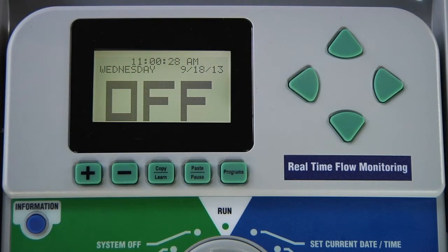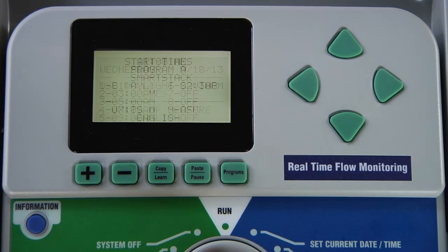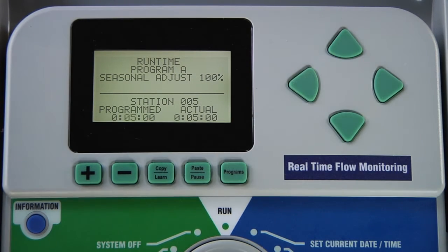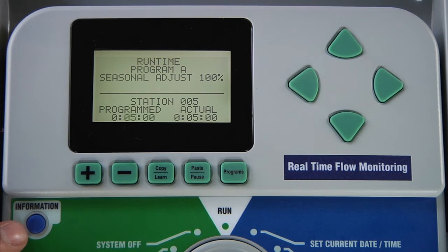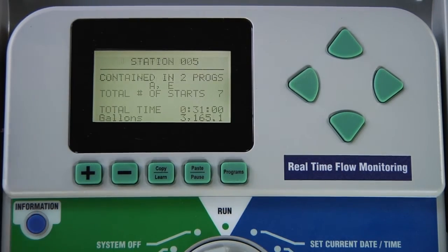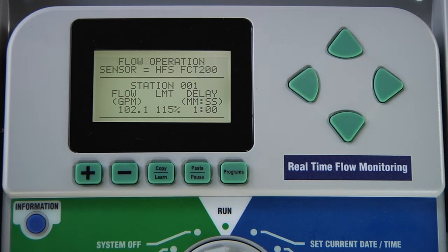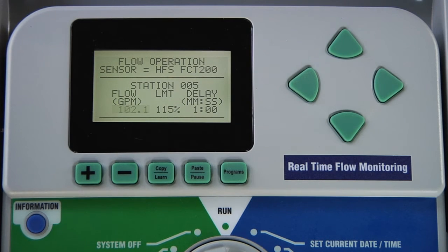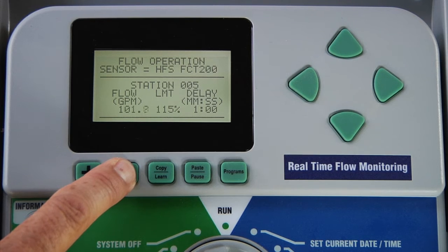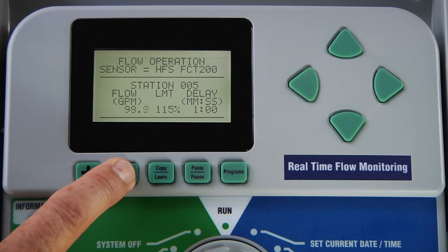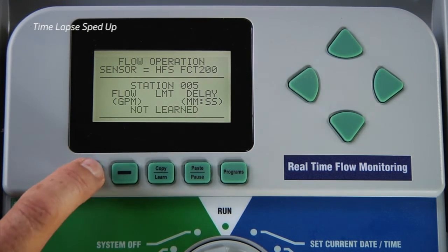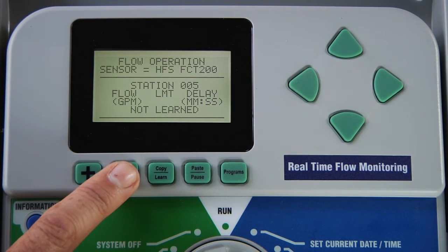To learn flow for a single station, make sure the station has a runtime in a program. Go to Set Station Runtimes and use the up arrow to go up to Station 5 and verify that it has five minutes shown. From there, hold down the blue info button, go to Set Flow Monitoring, and select Edit Learn Flow with the plus button. Use the up arrow to go to Station 5. We see it has a flow value already, but we're going to zero that out down to Not Learned so that it is the only station that will go through the learn process. Now we're at Not Learned for Station 5.